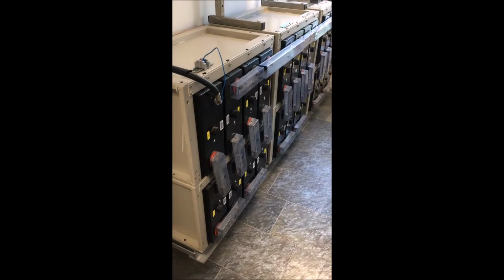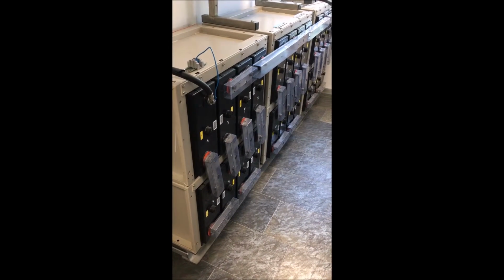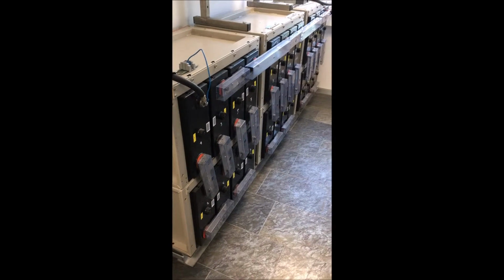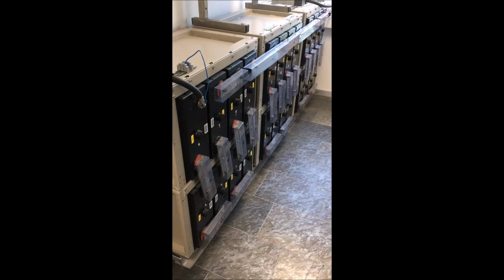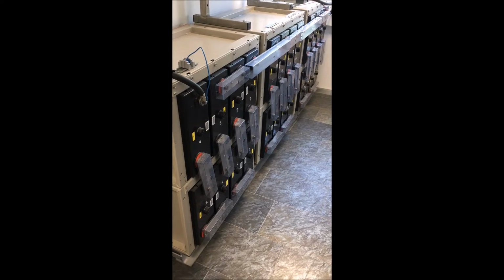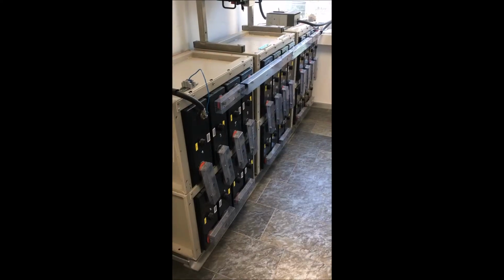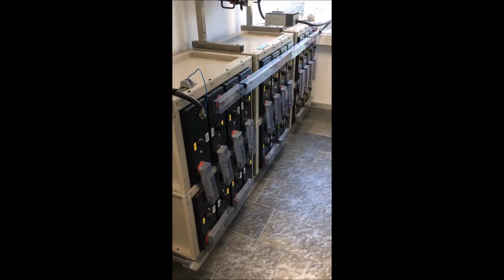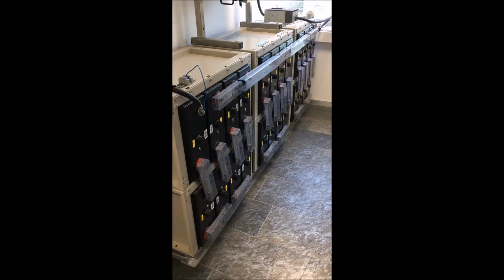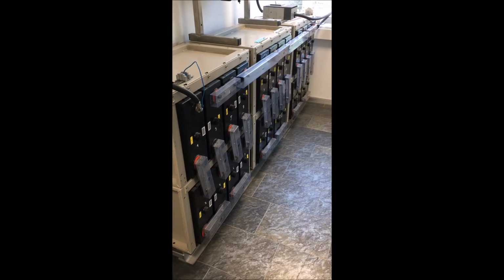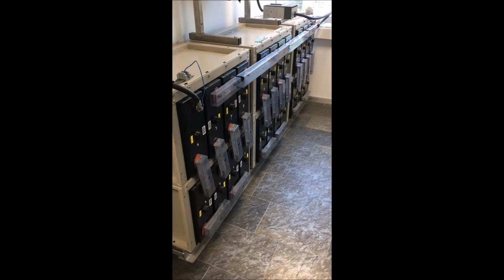Also, it should be noted that the batteries do not need any water refilling and that therefore the battery maintenance is minimal, which reduces the overall operational cost. The battery set which you see in this picture contains a net energy of 50 kilowatt hours, which can be extracted from the batteries over a time of 8 hours.